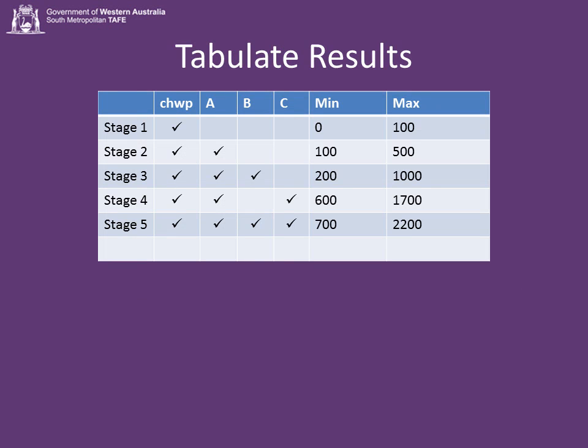From the graph then, I build a table of what each stage represents, what chiller will be on, and the maximum and minimum capacities of that stage. I add a stage 0, which is no cooling at all. Oh, and I turn the table over to match the one we had with the pumps. As I said before, I like to have an overlap.